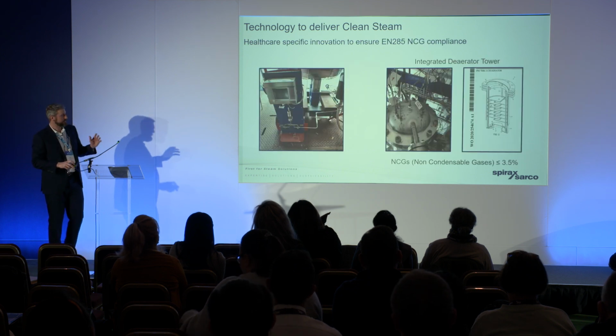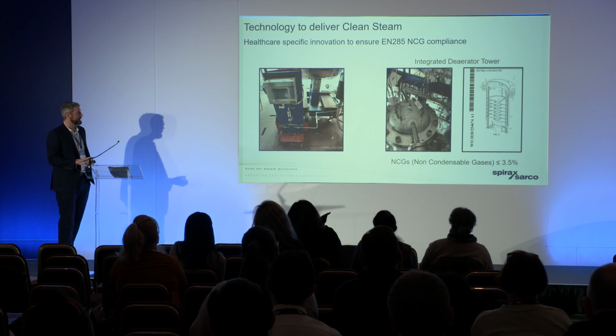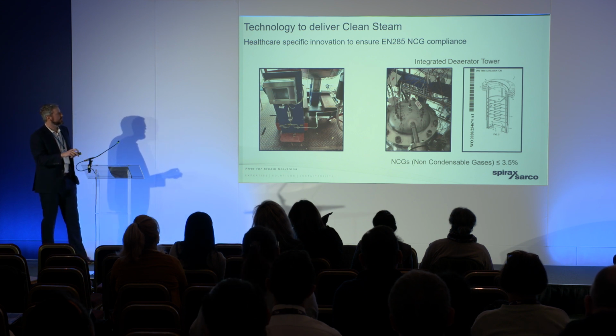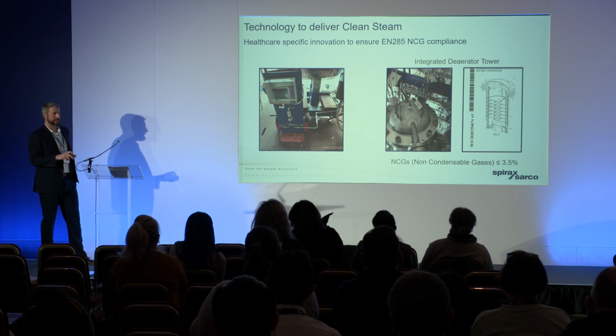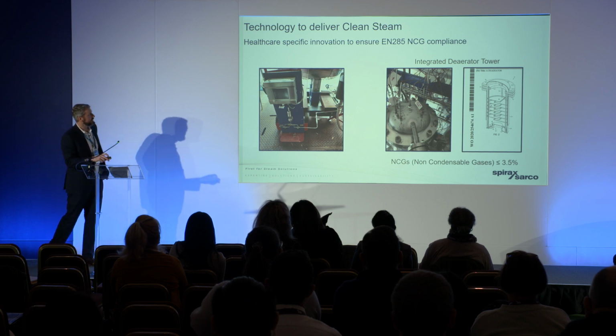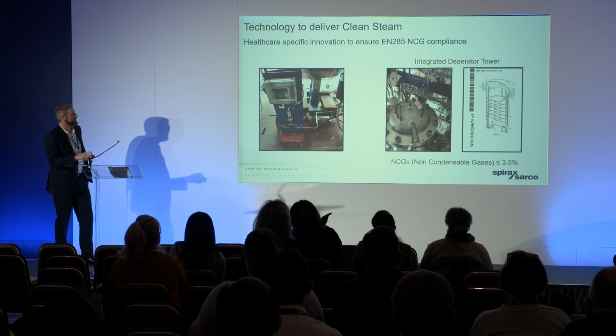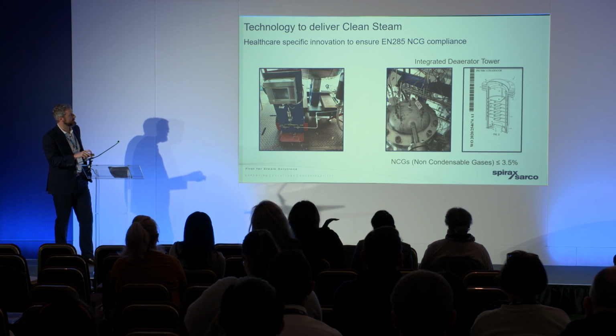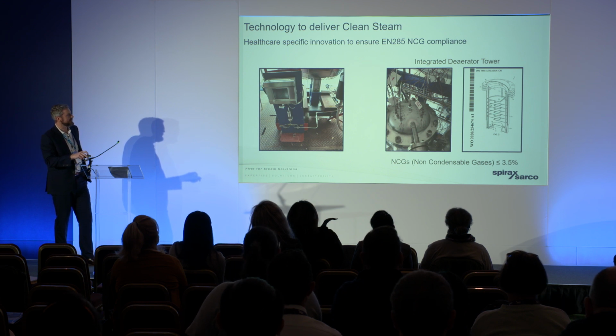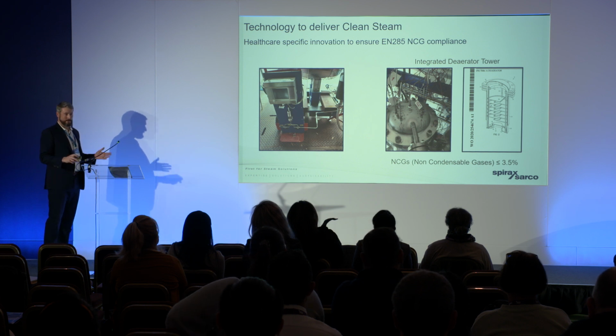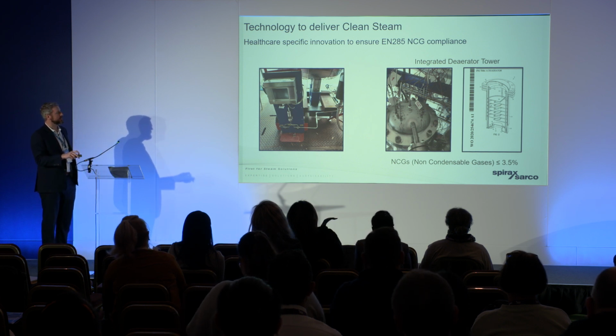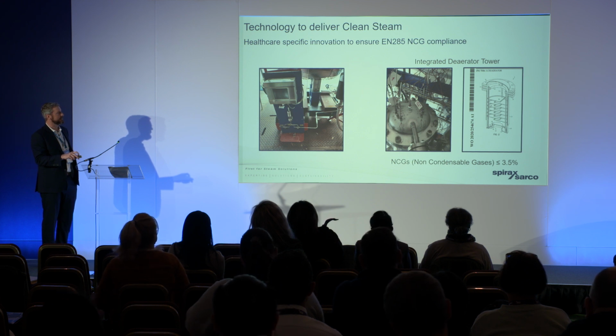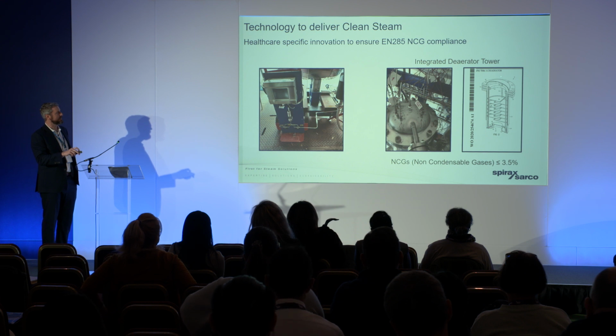This here, so we've talked about steam dryness and how we were able to prove that out with dynamic load conditions. We've also introduced a deaerator tower, which is a degasser. So this is how we achieve our non-condensable gases. So this is a picture of our patented technology. And you can see here that we had a thermocouple onto the test unit where we were able to measure the temperature of the water as the feed water cascaded through these different trays here. So we were able to test this across all the load conditions to prove that we were getting the adequate temperatures and contact time to remove the gas which would be vented off the top of this deaerator.